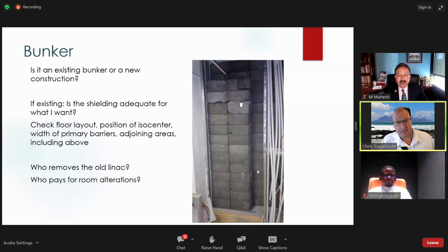The picture I have here actually happened to us. The floor plan didn't match what was actually built. When we measured behind this wall, we had 1 millisievert per hour, and we had to add additional shielding blocks because the ISO, or the primary barrier, was not sufficient. We hadn't specified this, so it became a hospital problem.